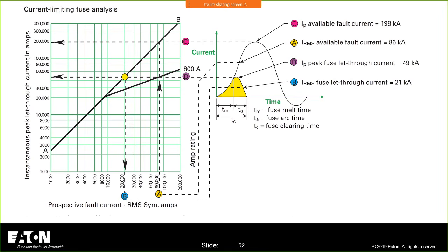I could translate this into incident energy reduction. I could translate this into a lot less equipment damage, etc. It's just what is your goal, and if you're trying to increase the short circuit current rating of, say, a piece of equipment that has a circuit breaker in it, I can't use this method. I can, though, say that I've reduced the incident energy and I've reduced the hazard. I just can't increase the short circuit current rating of a piece of equipment that has a circuit breaker inside.